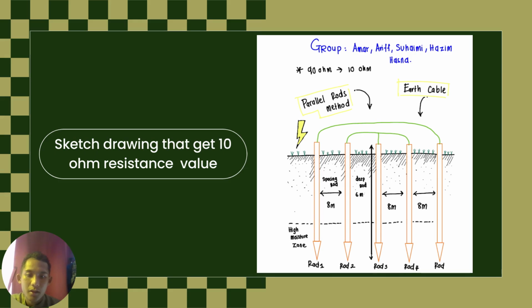So if the depth is 6 meters or 4 meters, the spacing we need is 2 times more, which is 8 meters. It depends on the depth of the rod because this way will produce lower resistivity. So as you can see, we put 5 rods in parallel, the depth is 6 meters and the spacing is 8 meters. This will increase the conductor and will produce a lower resistivity value.